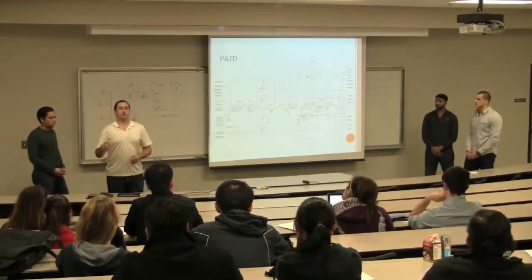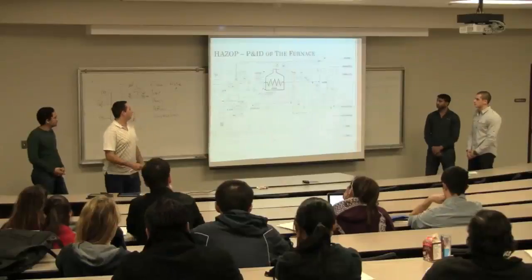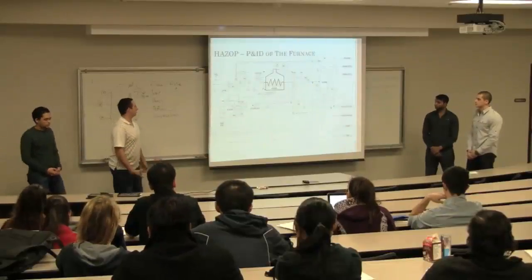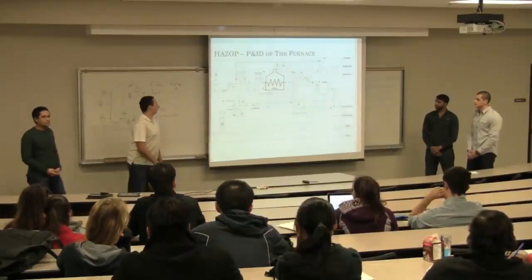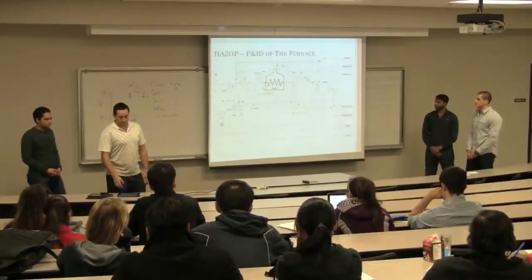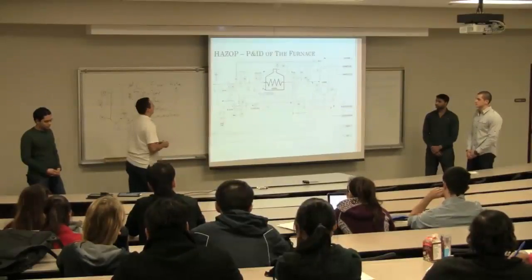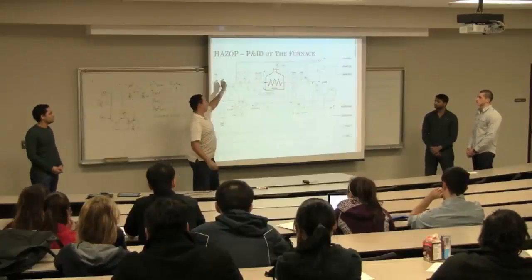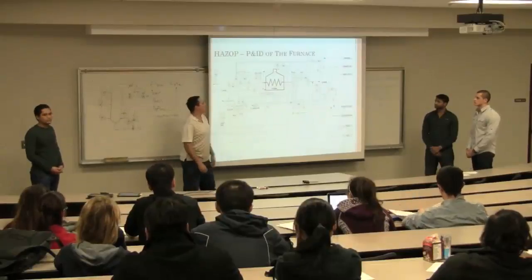And it'll just be wasted money spent on heating the water through the process. So here's a blown up view of just around the OTSG. As you can see, we've got a bunch of redundant valves and control loops that are installed, level sensors and pressure sensors. So for our HAZOP, we decided to focus on two nodes, which were the flow inlet into the OTSG, along with the point where the mixing was for the fuel and the air.